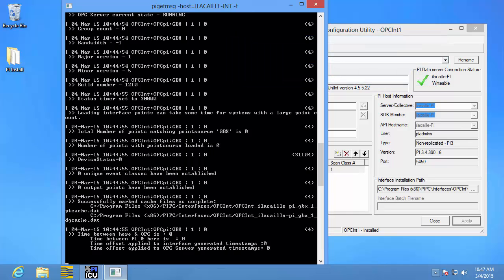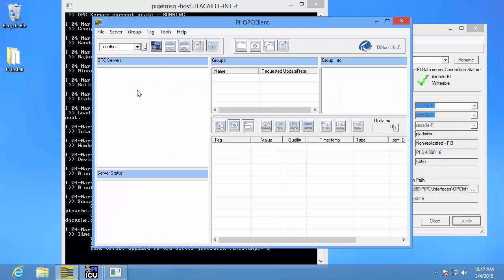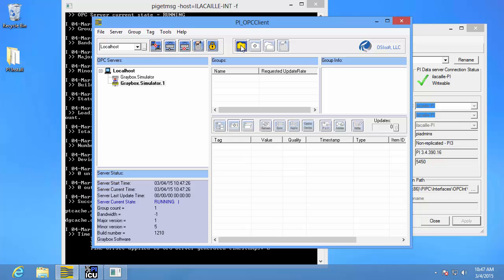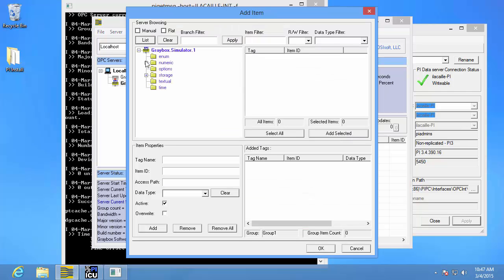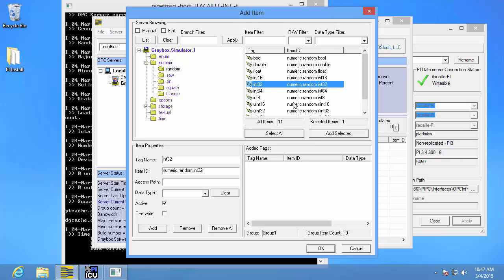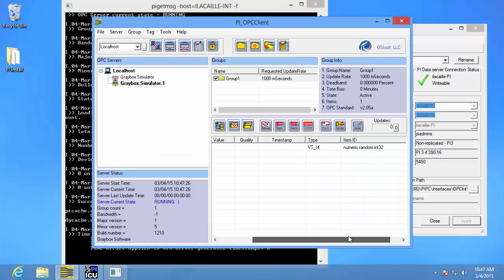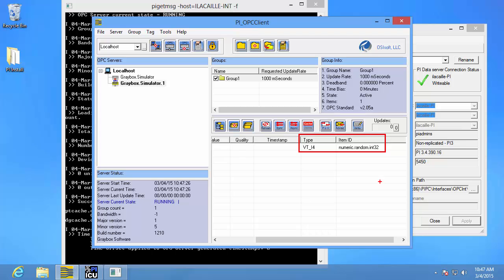To start, first we need to choose which data we'll be collecting, so we need to go back to our PI OPC client tool. I need to connect to my OPC server and create a group. I'll browse my OPC server and find the item that I want to collect data for, add it to my group, and hit OK. Here is what I need to create my PI point — I need to know the type and the item ID of my OPC item. Make sure to take a screenshot or write this down.